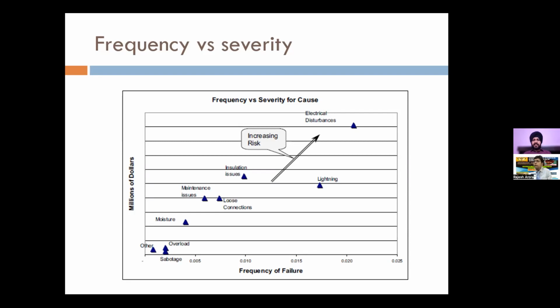And the least issue which is faced is overloading or sabotage, because particularly in India, our transformers, if we talk about the transmission sector, are mostly N-1 compliant. So overload is not an issue which we have faced. Of course, in the sub-transmission or distribution network, overloading is a relevant issue, but this frequency versus severity plot is only from a transmission sector point of view. So here we can see that overload and sabotage are causing the least number of failures and least damage, in terms of the magnitude of the financial losses to the utility.